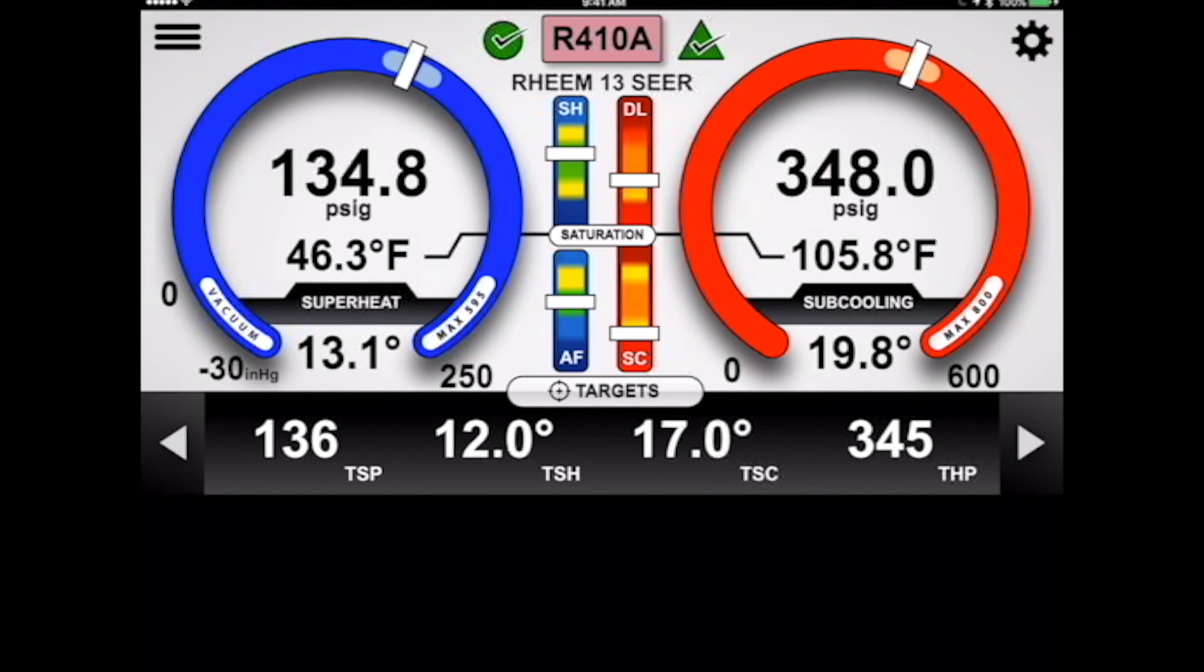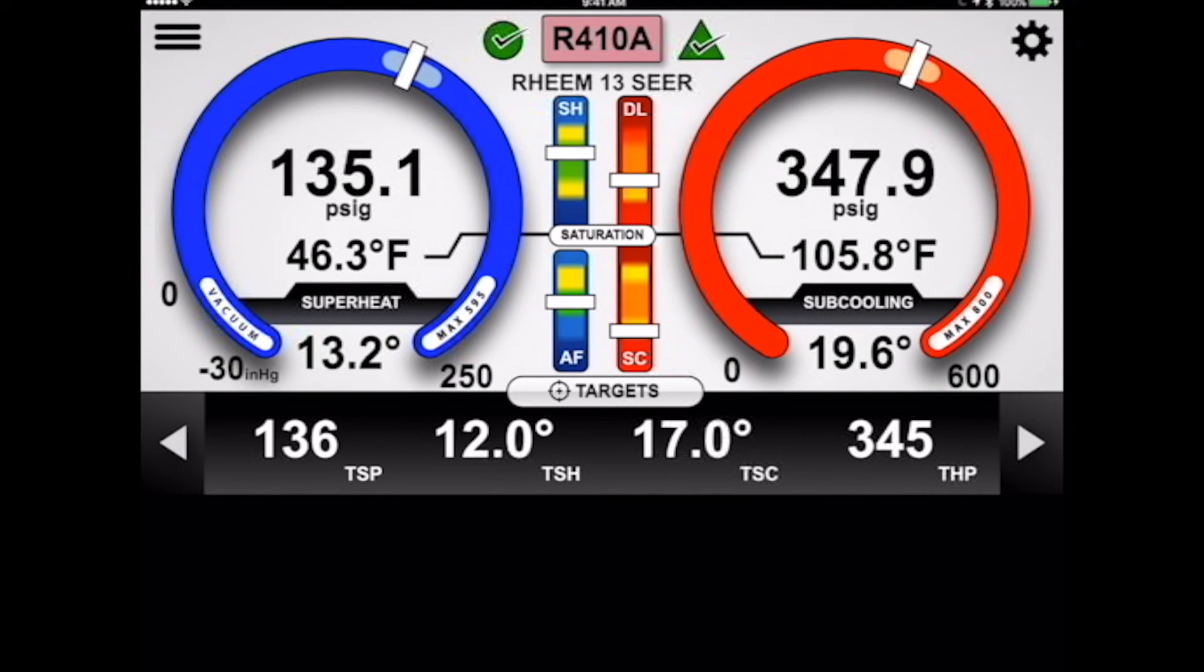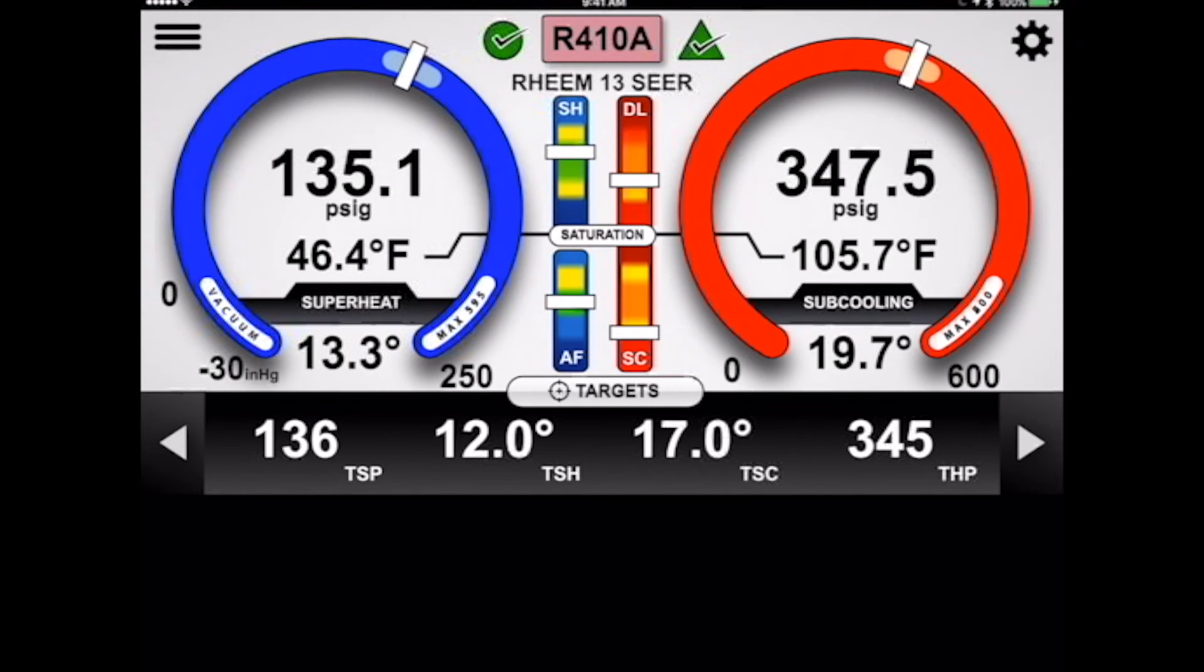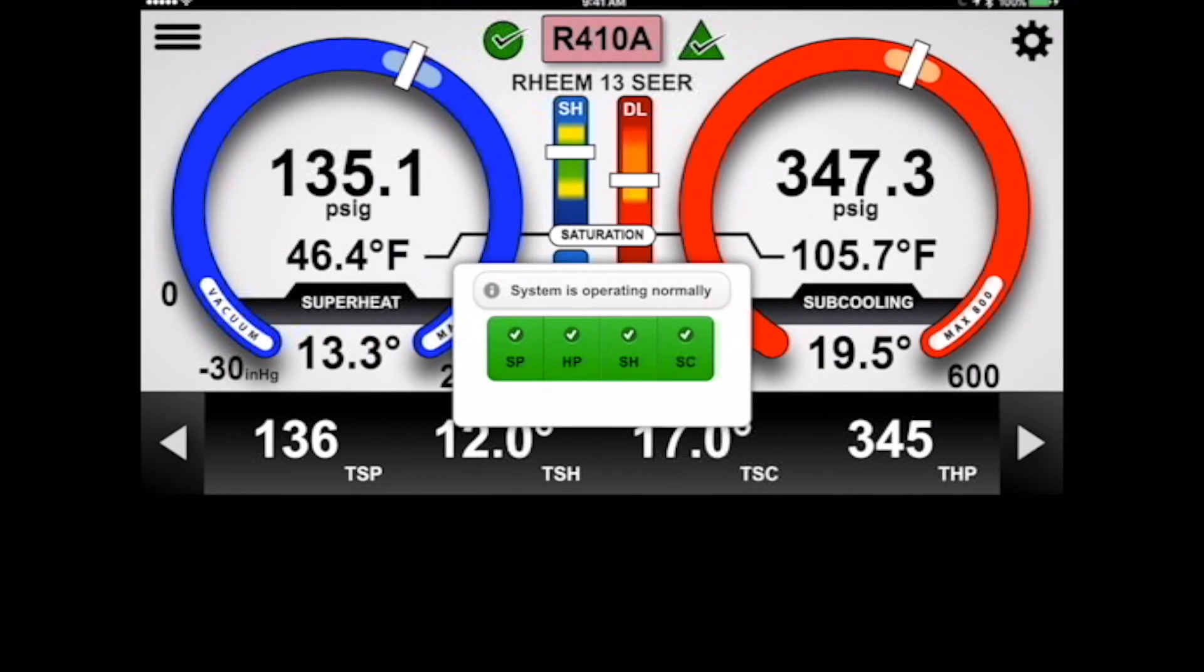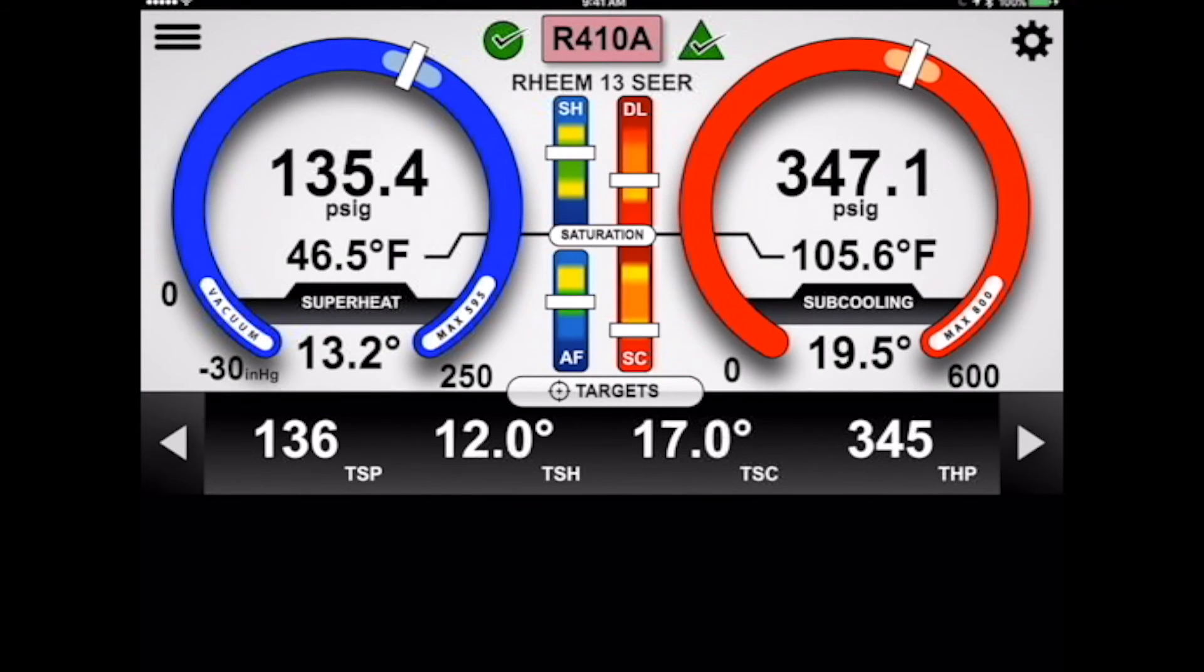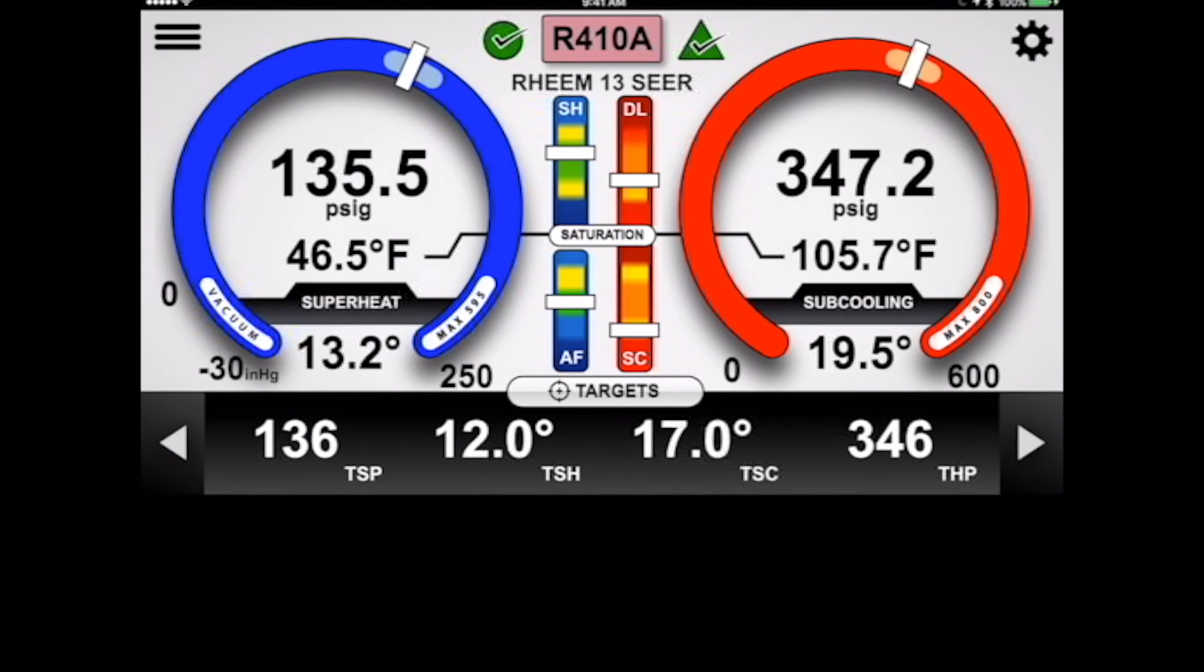You can see that we have a 17 degree target for our subcooling. We're at 19.8. So we're right at the threshold of maybe being a little bit overcharged. But it's within the allowable plus or minus 3 degrees, so we're actually pretty good. If we tap on that troubleshooting triangle now, you can see this is a normally operating system.